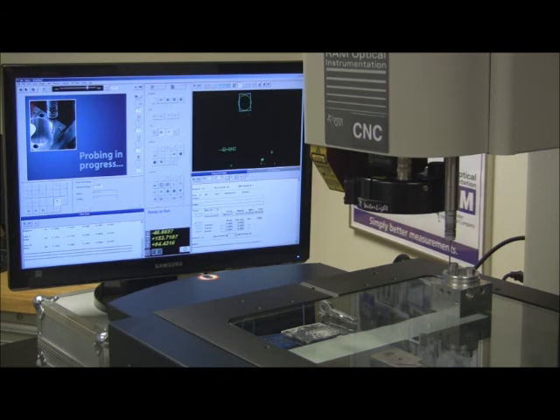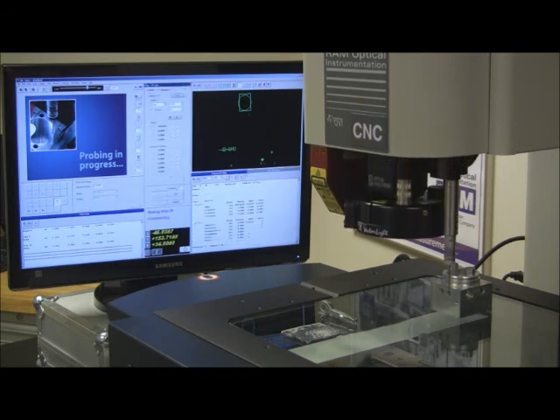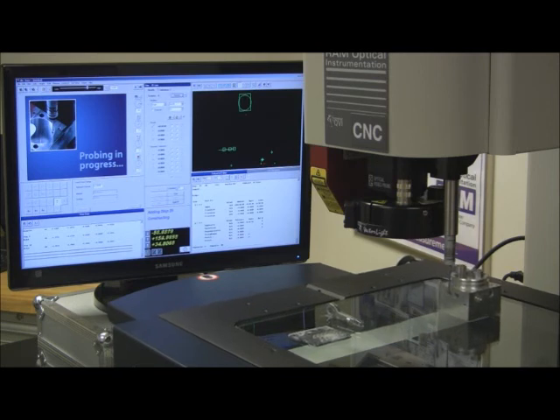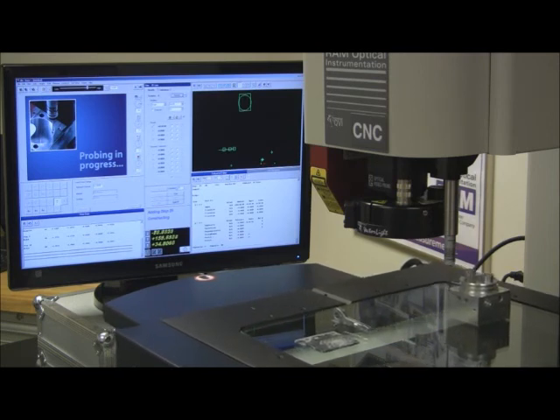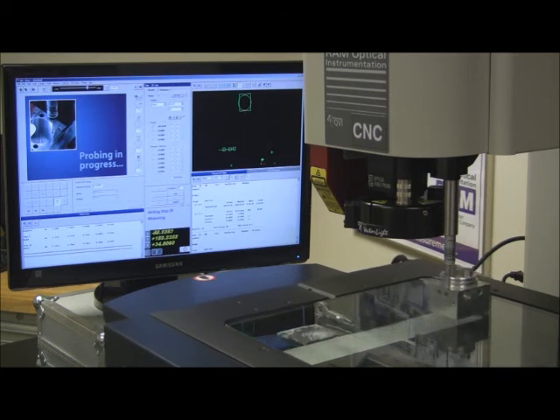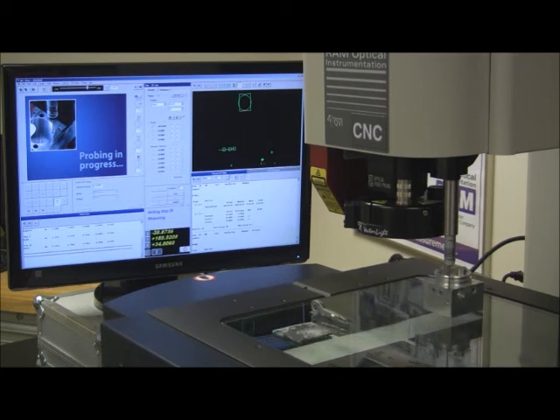If I say OK and I say I want to measure a line now, to measure a line I have to have a minimum of 2 points. So I'm going to come down on the part. Sorry, I selected construct line instead of measure line. I'm in measurement still. Come down on the part and I touch and it automatically backs off the back off distance, which right now we have set as 2.5 millimeters.